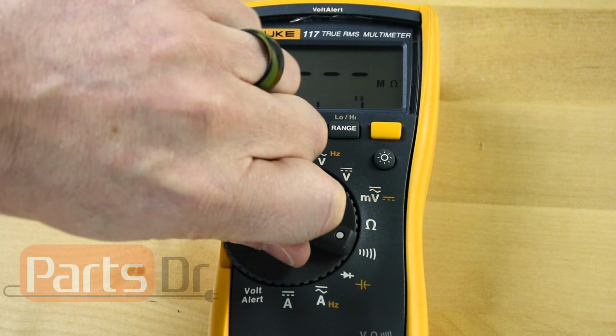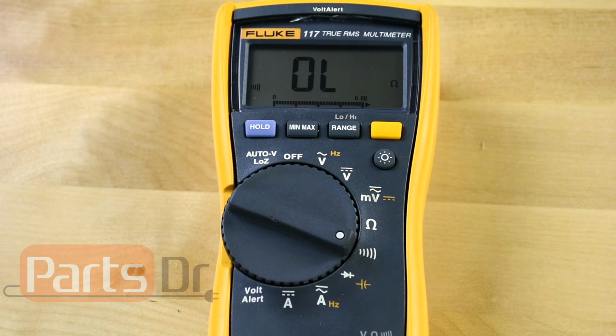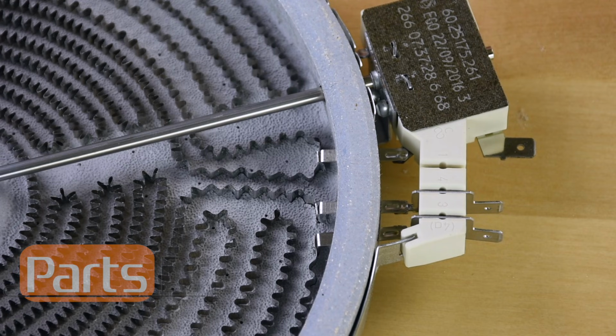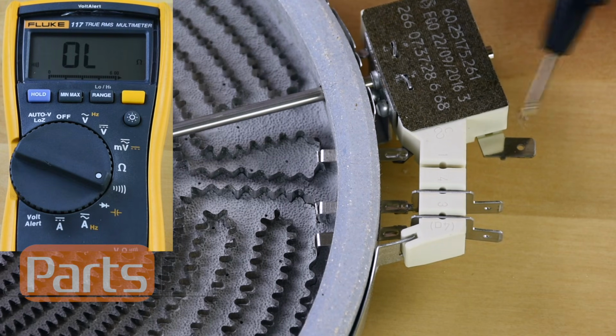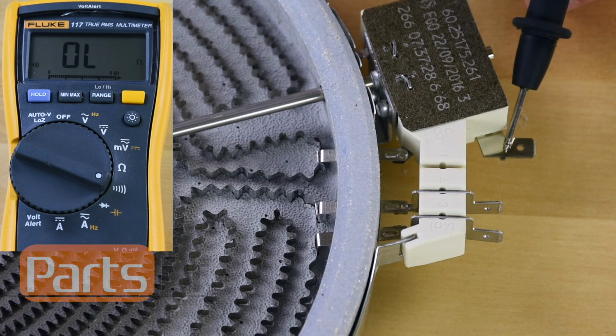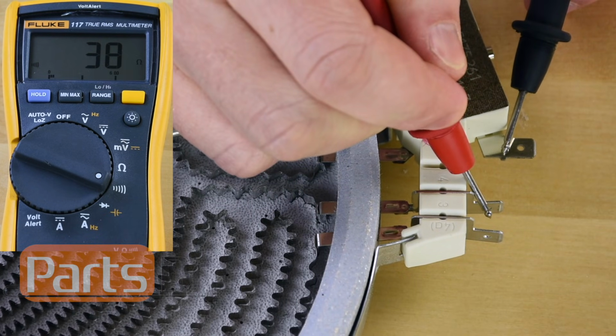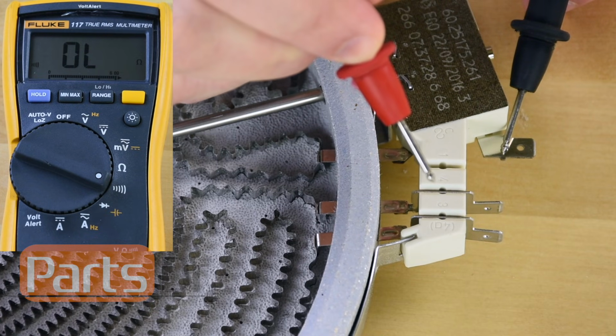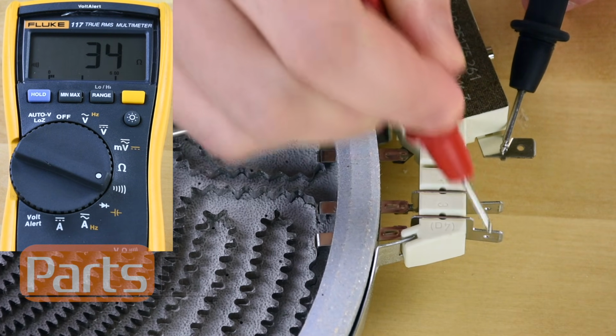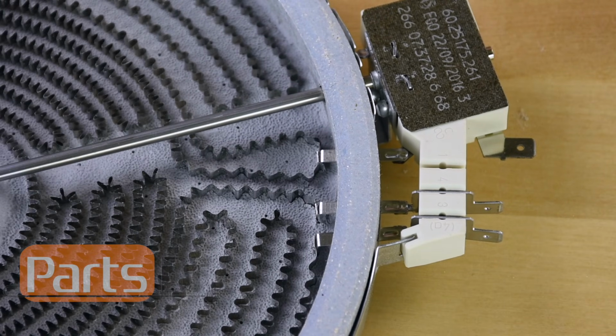If your multimeter has the option, turn your meter to the continuity setting. To do a continuity test, you will need to place one of the probes on the common wire terminal of the heating element and the other probe on one of the other terminals. Next, repeat the same process on the other wire terminals. If the element is bad, the meter will not make any noise, and if the coil you are testing is good, the meter will make an audible beeping noise. Since a multi-coil element has separate heating coils, it is possible for one coil to be good and the other to be bad. If one coil is burned out, then the heating element will need to be replaced.